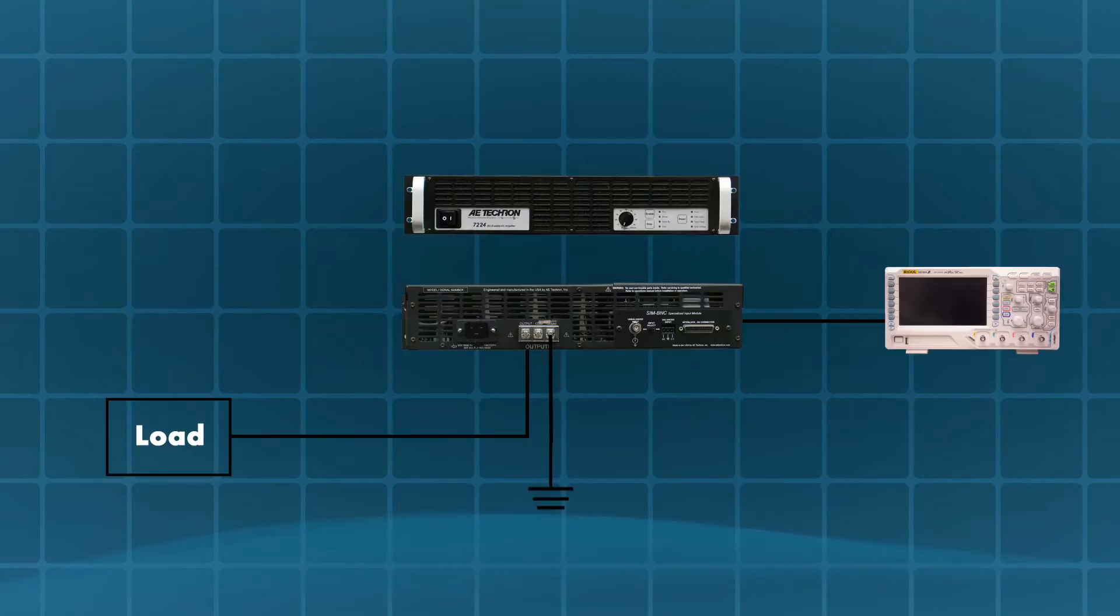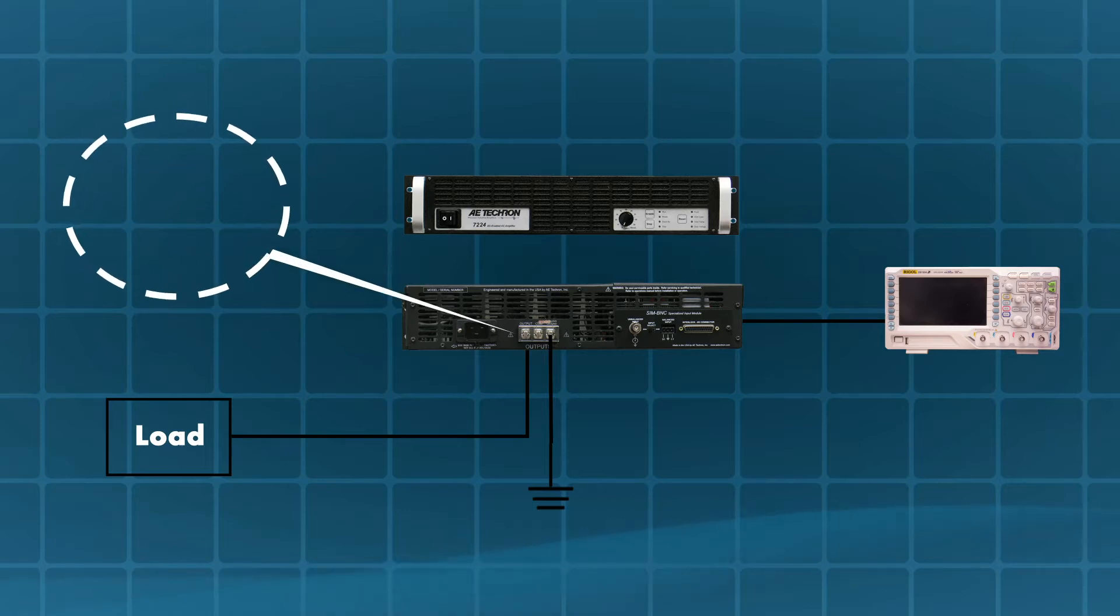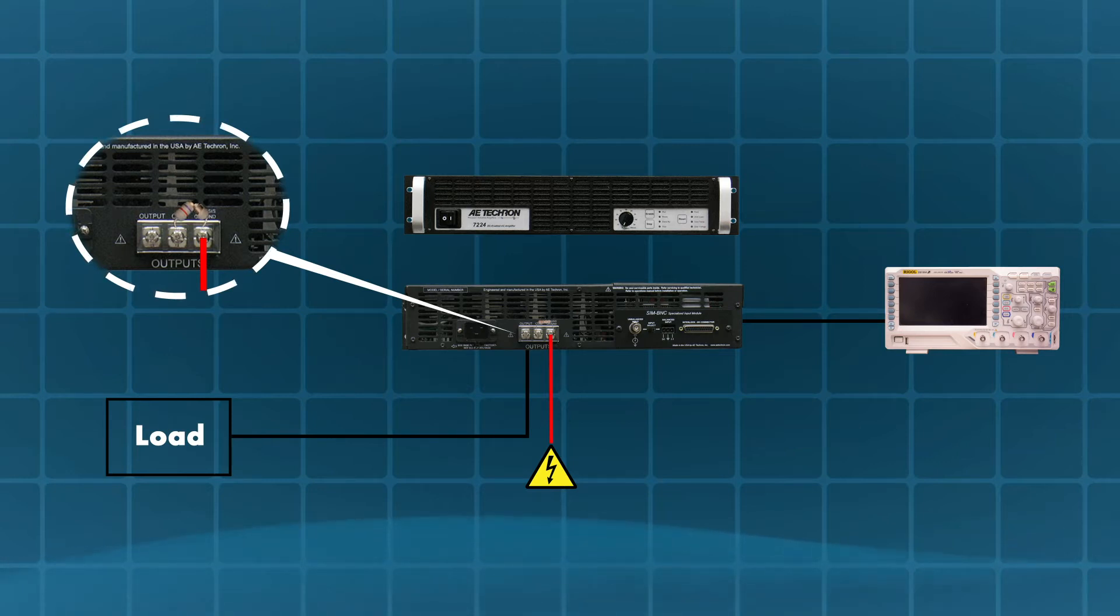Levels in excess of this amount can cause damage to your AE Techron amplifier, the signal source, and the DUT. If this resistor fails, always stop. Carefully review the AC mains ground connections, connections of each piece of equipment in the system, and replace the 2.7 ohm resistor.